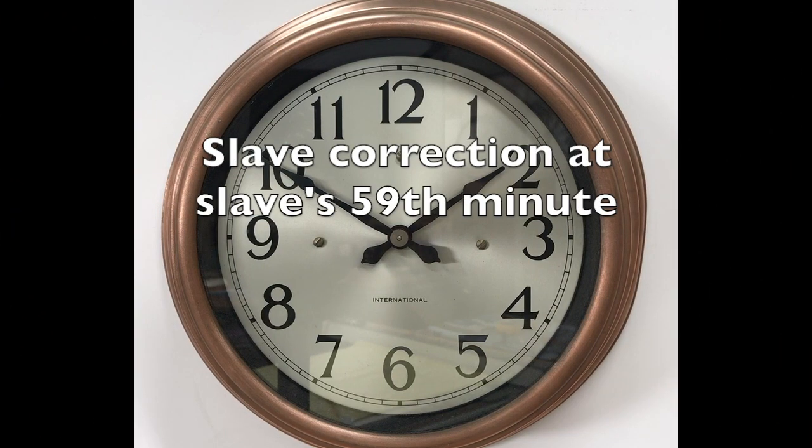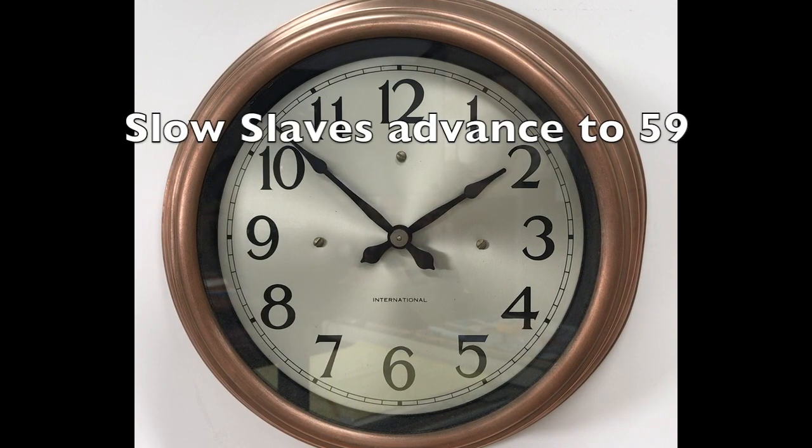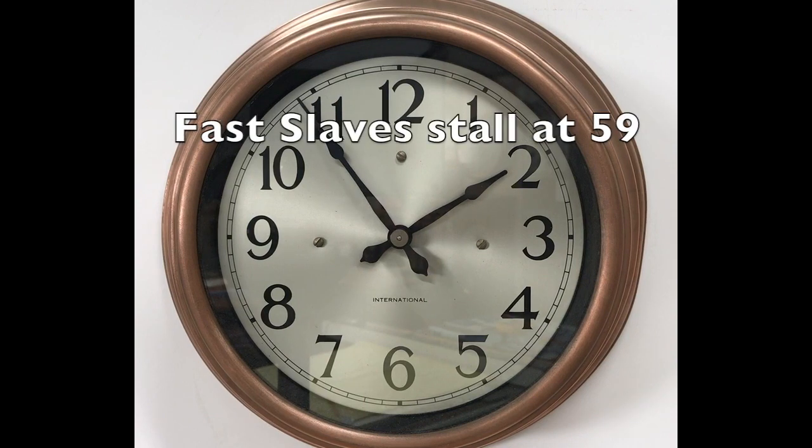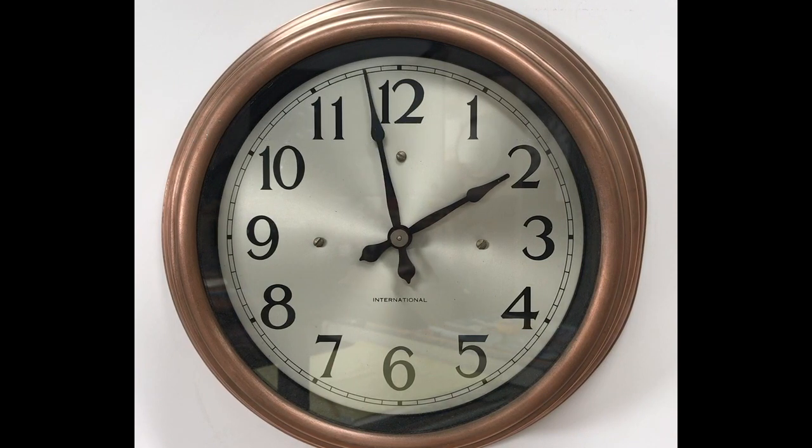Slave correction is at the slave clock's 59th minute. Here a slow slave is advancing to the 59th minute. Fast slaves stalled at the 59th minute and on time slaves arrived at 59 at precisely master clock time. I know this sounds pretty complicated but stick with me and I will explain.